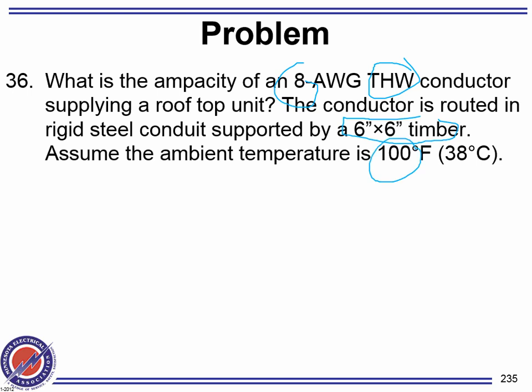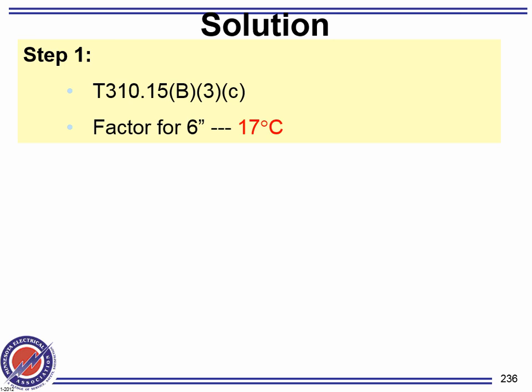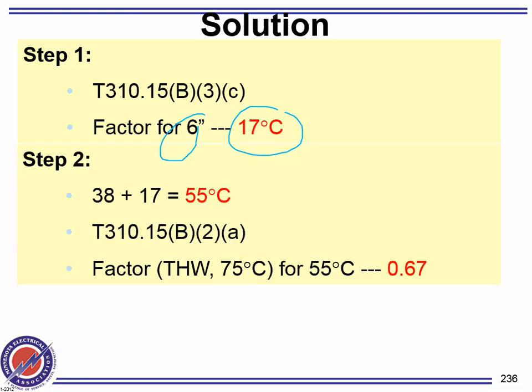So what do you need to do? You need to add a temperature adder. All right, gentlemen. For 6 inches, we're doing Celsius here. Don't ask me why. 17 degrees Celsius. And then you add the 17 degrees to the 38 existing. That'll give you 55. You go to table 310.15(B) for number 8. That will get you a derating factor of 0.67. Right? Everybody understand that? We just added temperature.